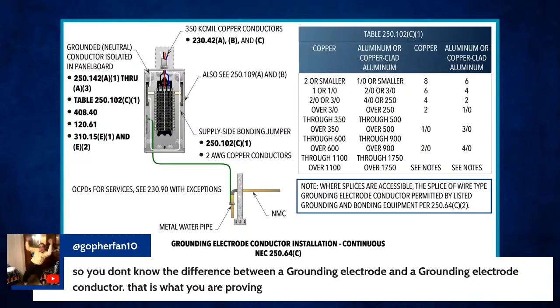Yeah, I mean, it doesn't matter, Jeremy. Like, you're trying to say apples and oranges are the same thing. It's not. It tells you right there in the code, dude. Like, no. The last sentence there says the grounding electrode conductor. It's not saying grounding electrode, Jeremy. Once again, you don't listen. Shall be sized for the largest grounding electrode conductor required among all the electrodes connected to it. Yeah. So it didn't say anything about that.